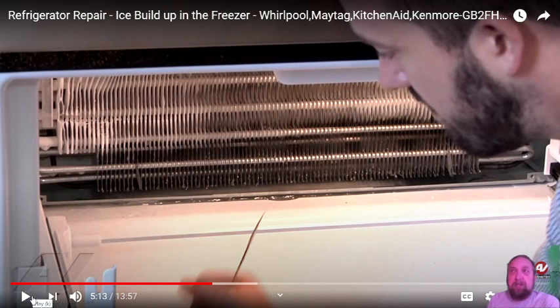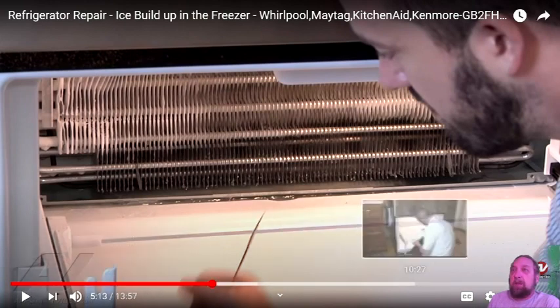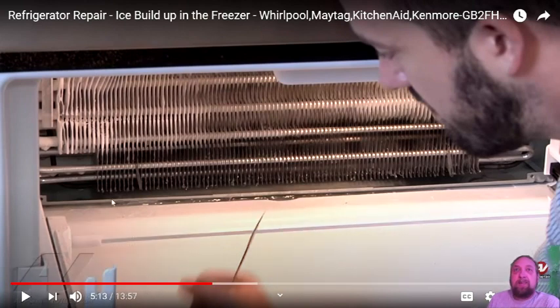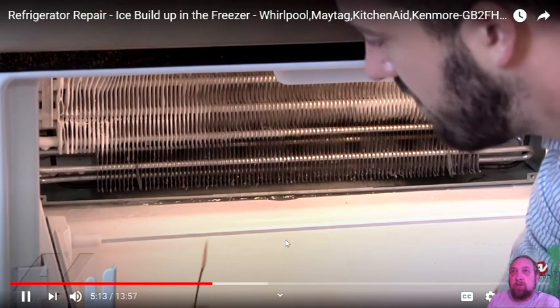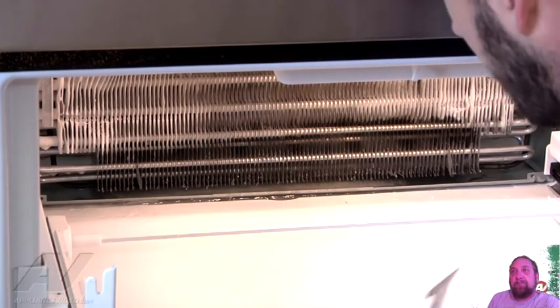Keep one or two beach towels on your truck, lay them in the bottom of the freezer here, take some hot water or some water and pour some water here. It'll only take a minute or two to loosen this ice up, and then with a plastic putty knife you can lift it up. If you use hot enough water, you'll be able to clear the drain. It looks like that one picture of the drain line that I showed you. All the ice at the bottom kind of cleared off first here.